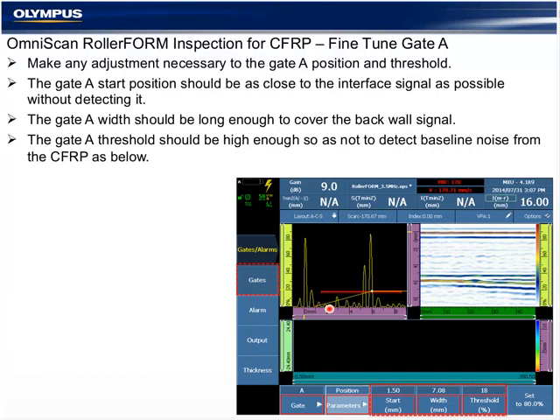There was a question about what options, if any, are available on the probe width. There are two options: a 32 element, a small version of the wheel probe, and the 64 element. The 64 element probe would be 64 total elements times 0.8. So if you were theoretically using a 1-element aperture, the maximum width would be 51 millimeters. With 4 elements, it would be about 48. In the follow-up presentation to this, and in the brochure that will be included with it, there are several options, and those probe details and specifications are laid out.